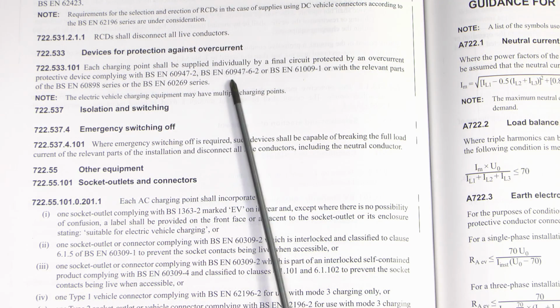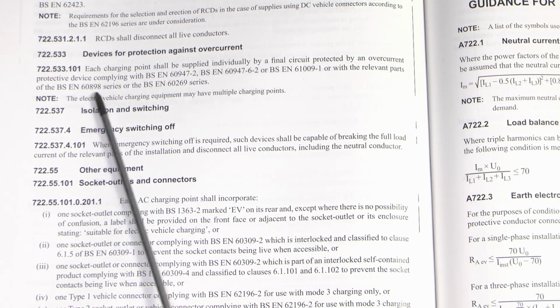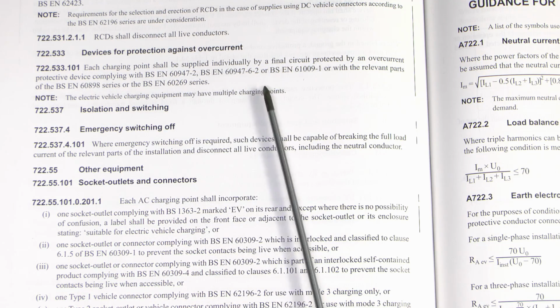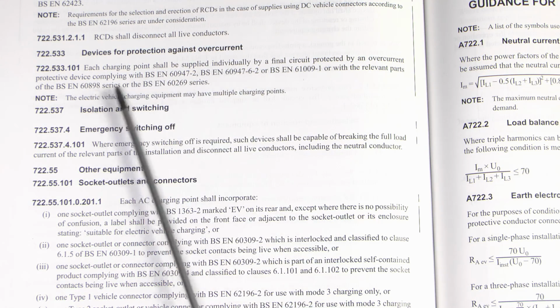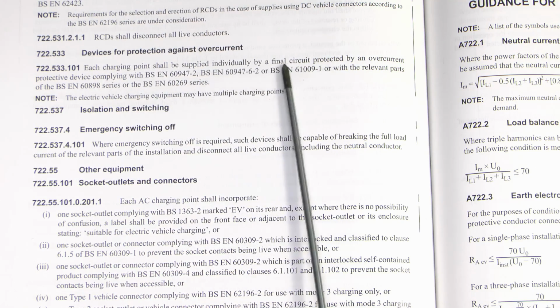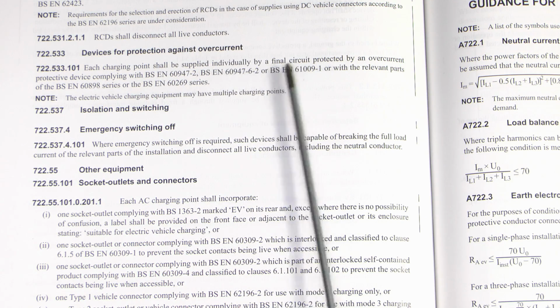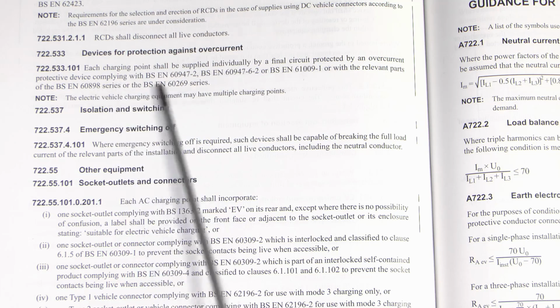That's going to be your normal circuit breaker in most cases, the 60898, and more typically it's going to be a 32 amp circuit there. And notably it needs to be an individual circuit, so if you're going to have, say, two of them installed, then they each need to have their own circuit and their own protective device.